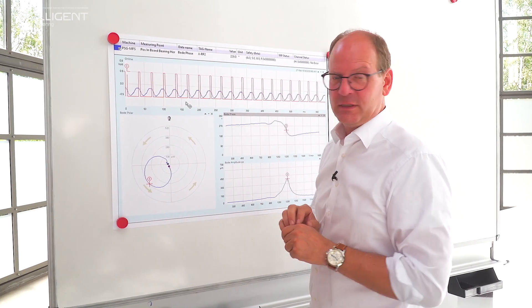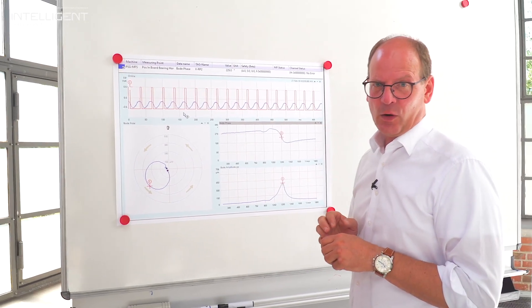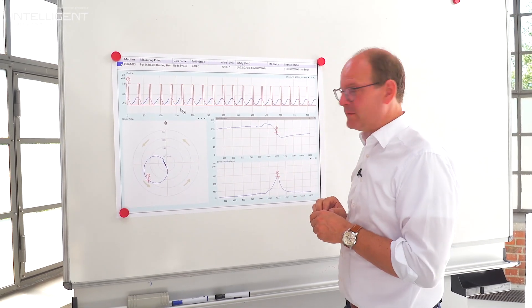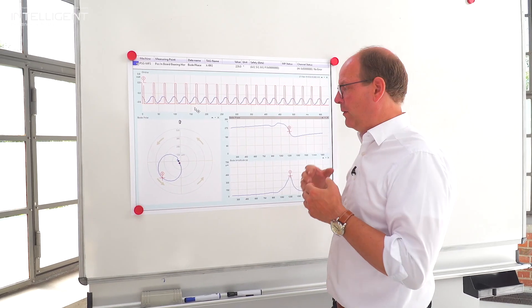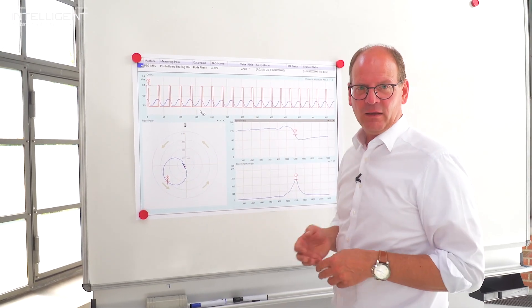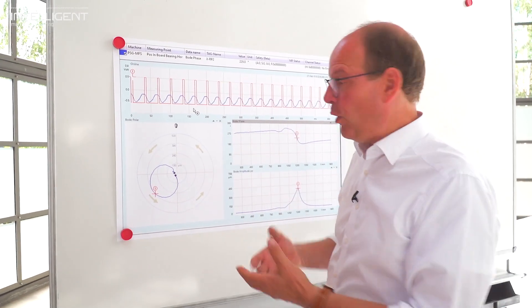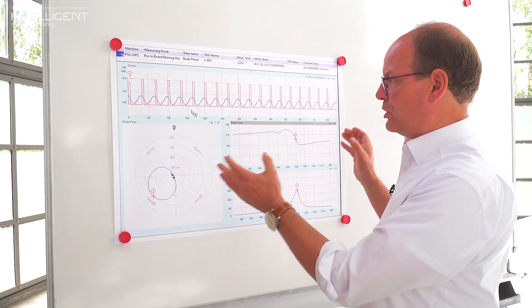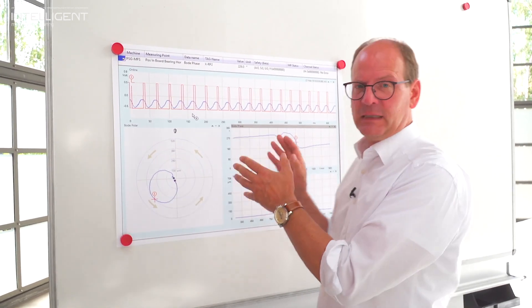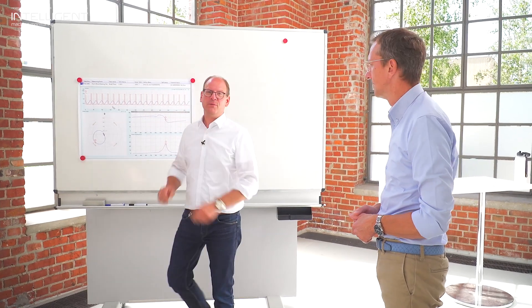This Bode Polar Plot is a very important tool you use during the run-up and coast-down of a rotating machine. This can also be used to detect oil instability, unbalance, misalignment, any kind of failure or problem with the gear coupling or in the gearbox. Any kind of failure we would like to detect during the start up or during the run-up and coast-down of the machine.